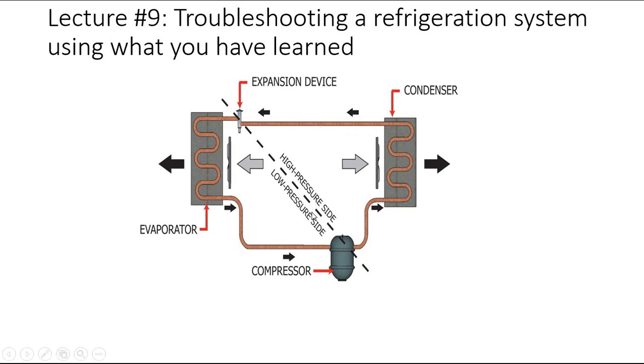The other thing you want to do before you get your gauges out is give a good look over to the refrigeration system. Look for leaks, generally in the condenser. If you see oil staining on the aluminum coils, that type of thing. Let's say everything's good—you've checked your evaporator filter, your condenser is clear, and you're still not getting the refrigeration performance you expect. Now it's probably a good time to put your gauges on and start taking your readings.